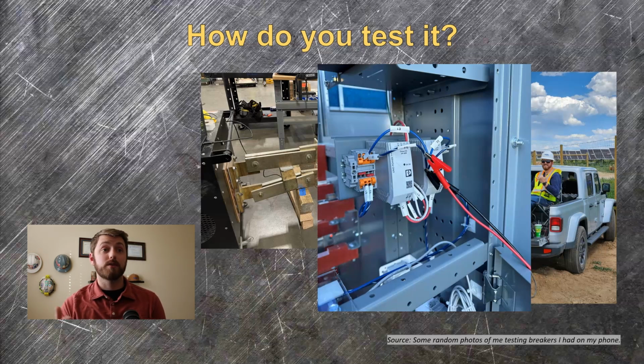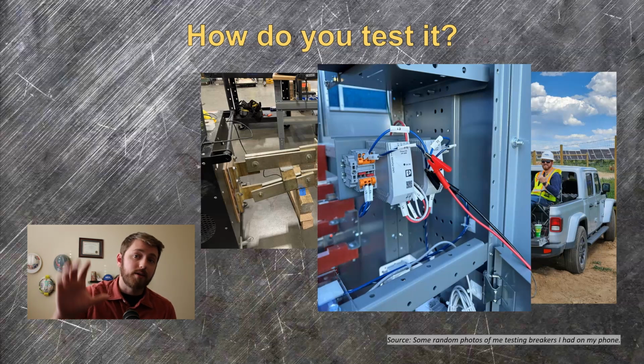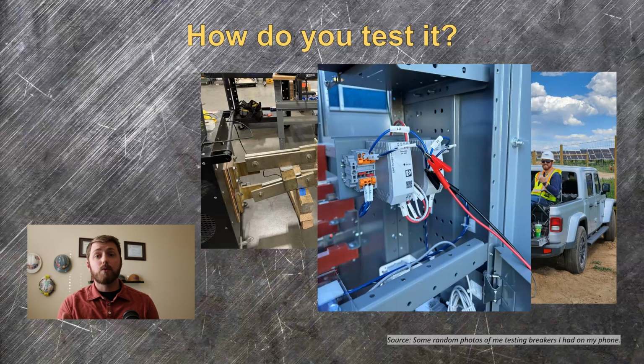During commissioning, once the breaker is in the gear and the bus is hot, it's your responsibility to verify that same benchmark. The maintenance mode comes on when the switch is toggled as the breaker sits in the gear. It needs to work under its own power in service. That's part of the test.